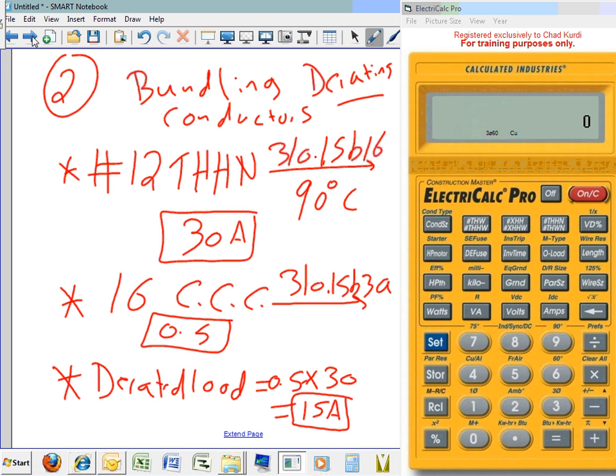Okay. So let me do this with the calculator. The challenge with the calculator, guys, is that it doesn't calculate the amps. It calculates conductors. You need to give it the amps, give it the load, to get the conductor. That's what the calculator does. You have to give it the load to get the conductor. Okay, so let's go give it the load.